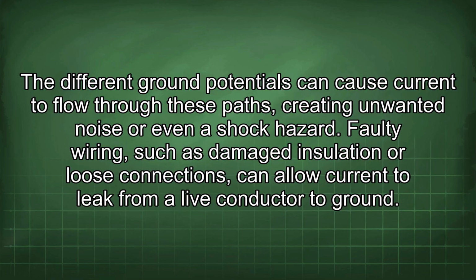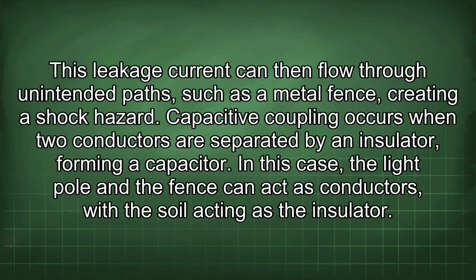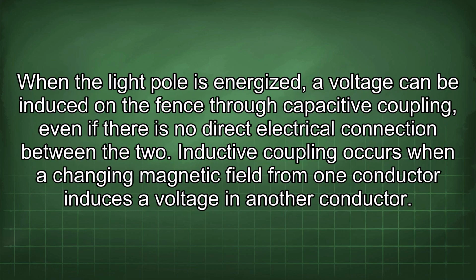Faulty wiring, such as damaged insulation or loose connections, can allow current to leak from a live conductor to ground. This leakage current can then flow through unintended paths, such as a metal fence, creating a shock hazard. Capacitive coupling occurs when two conductors are separated by an insulator, forming a capacitor. In this case, the light pole and the fence can act as conductors, with the soil acting as the insulator. When the light pole is energized, a voltage can be induced on the fence through capacitive coupling, even if there is no direct electrical connection between the two.